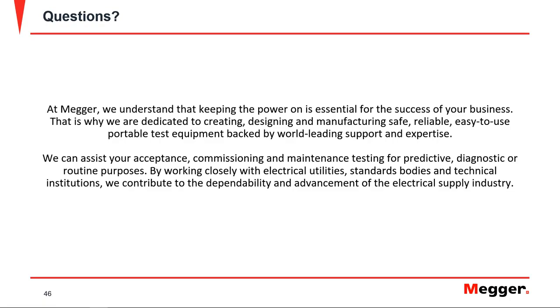All right, thank you. Volney, can we use this equipment to measure the contact resistance, bus bar resistance as well? Okay, that's another interesting application. When you do current injection, definitely you can measure resistance. However, this instrument doesn't do the measurement of the contact resistance or the bus bar resistance directly. In addition to injecting the current, you need to measure the voltage drop, the millivolt drop, across the resistance that you are interested in measuring.